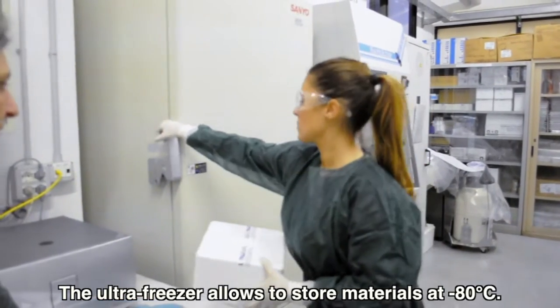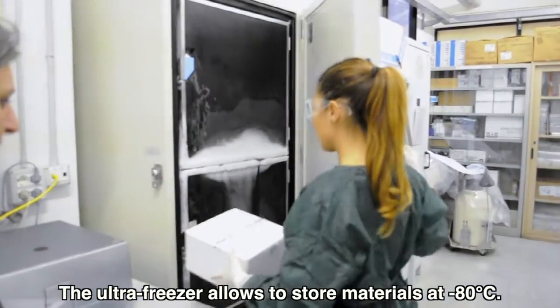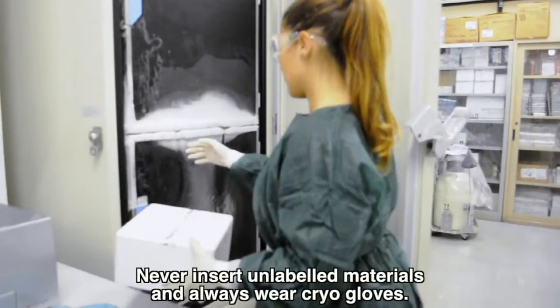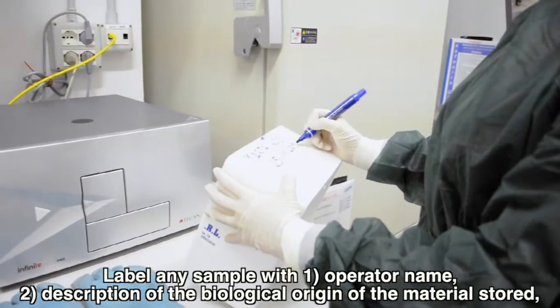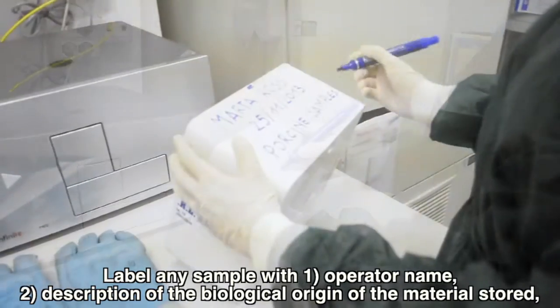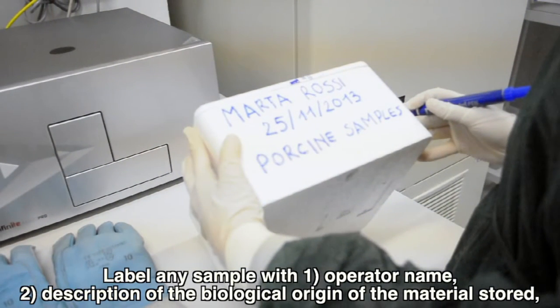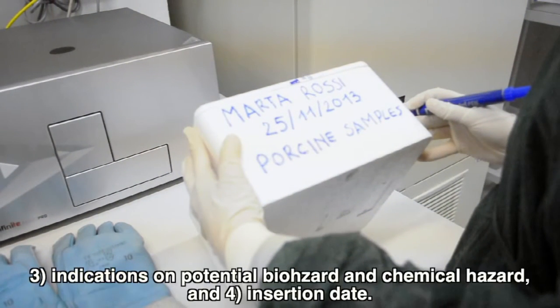The ultra freezer allows to store materials at -80 degrees. Never insert unlabeled materials and always wear cryo gloves. Label any sample with operator name, description of the biological origin of the material stored, indications on potential biohazard and chemical hazard, and insertion date. Incorrectly labeled materials are periodically disposed as waste by safety officer.